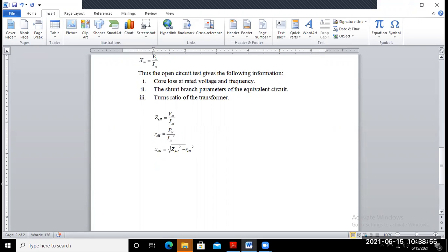This is a 200 kVA, 11,000 divided by 400 volt, 50 hertz transformer, connected in delta star. The open circuit parameters are given here: 400 volt, 9 ampere, and 1.5 kilowatt.